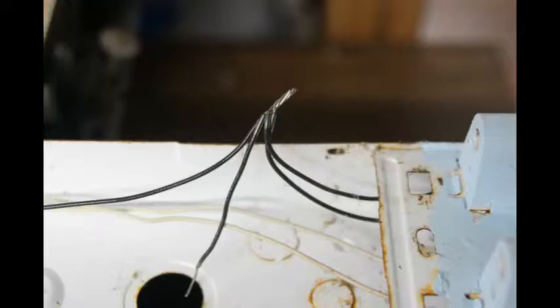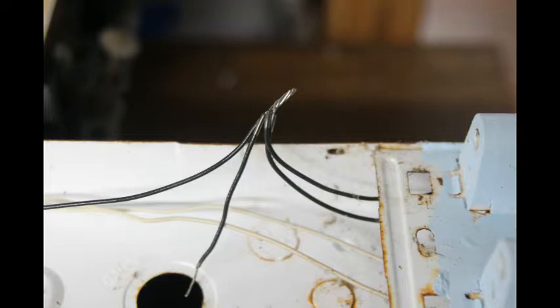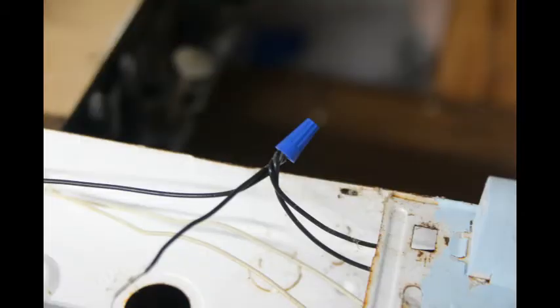However, if you have a non-shunted tombstone, it doesn't quite work out that way. What you need to do is to make both of those black wires and both of those neutral wires on this end connect to your input power and your input neutral. I cut the long black wire coming from one side of the tombstone and stripped the wires, introducing a fourth wire and wire nutting all four of these together.